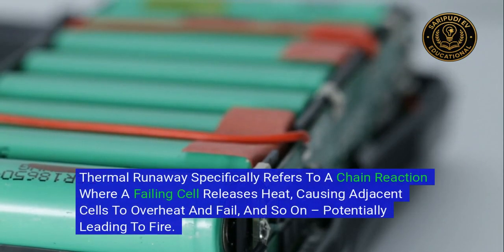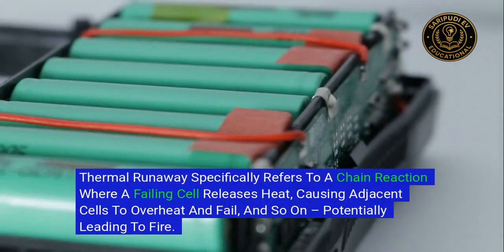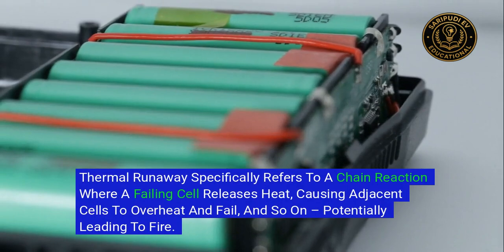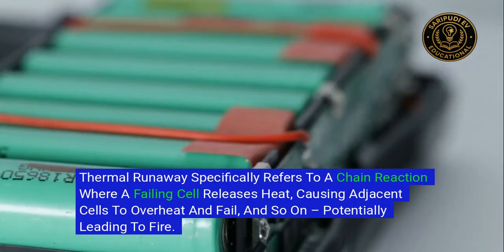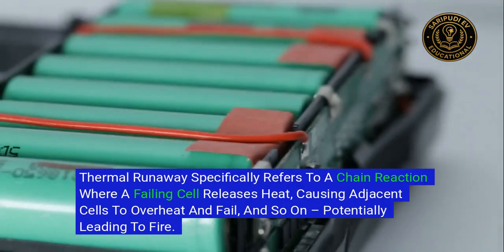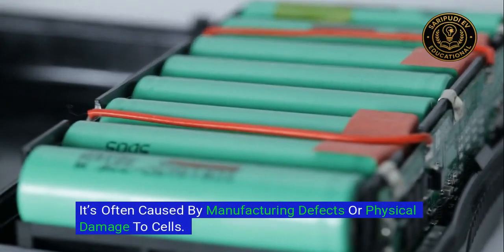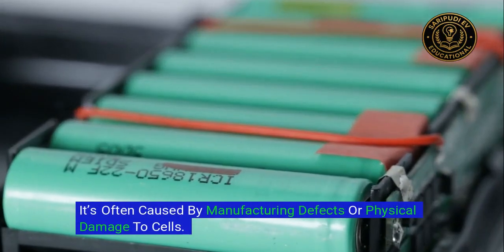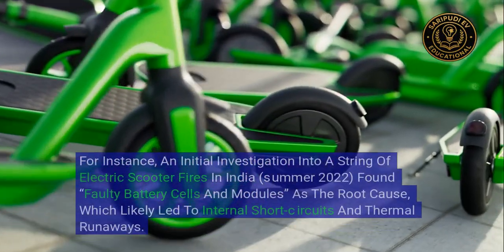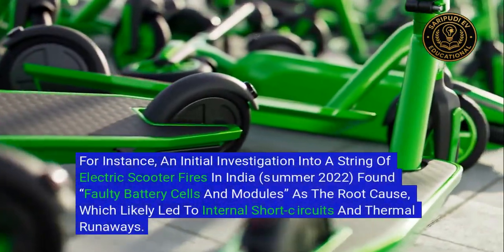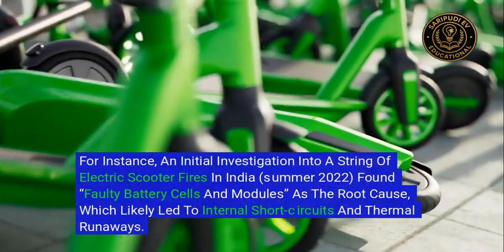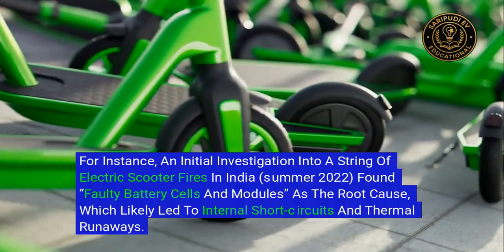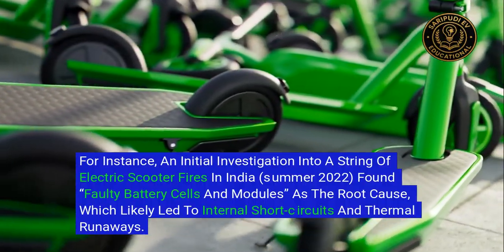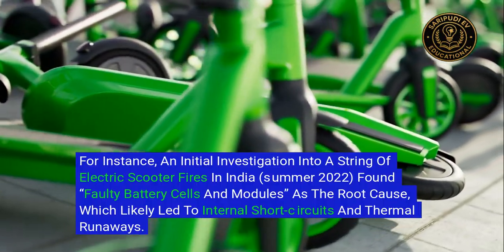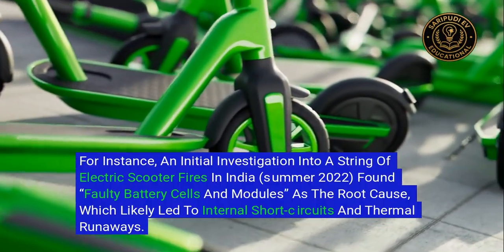Thermal runaway specifically refers to a chain reaction where a failing cell releases heat, causing adjacent cells to overheat and fail, and so on, potentially leading to fire. It's often caused by manufacturing defects or physical damage to cells. For instance, an initial investigation into a string of electric scooter fires in India, summer 2022, found faulty battery cells and modules as the root cause, which likely led to internal short circuits and thermal runaways.